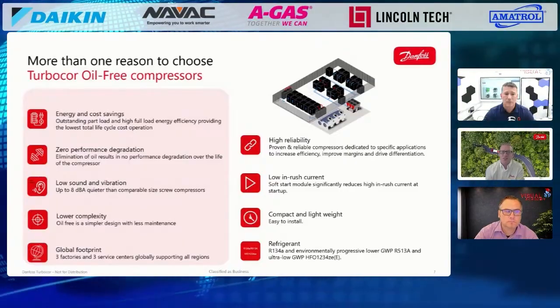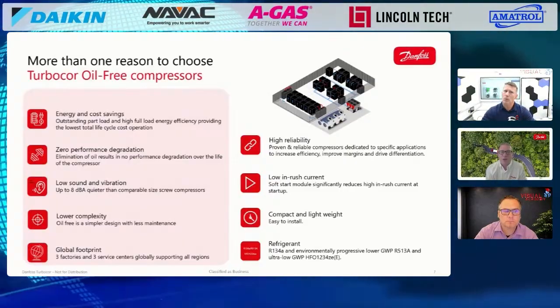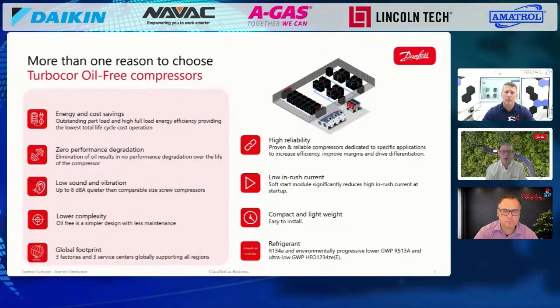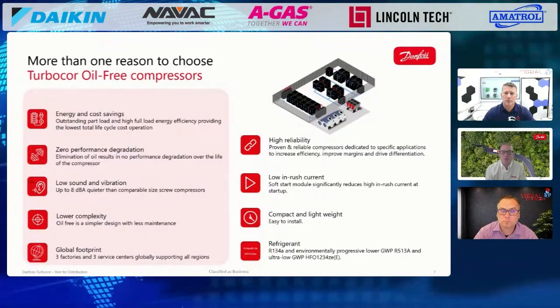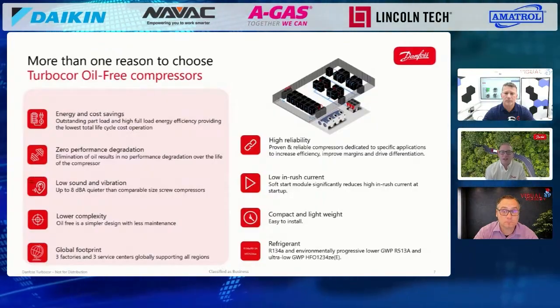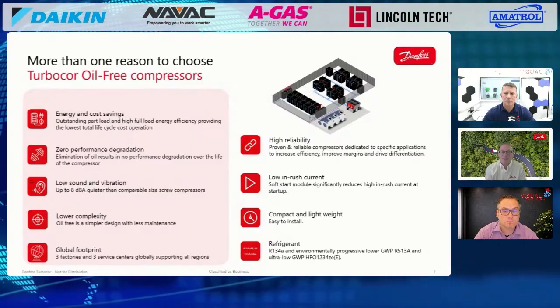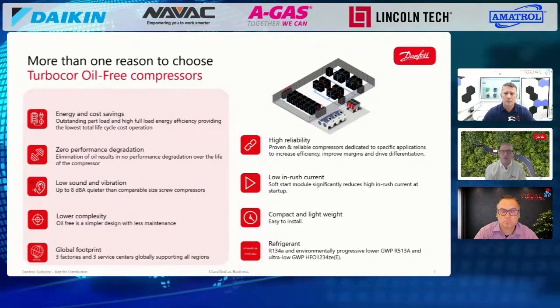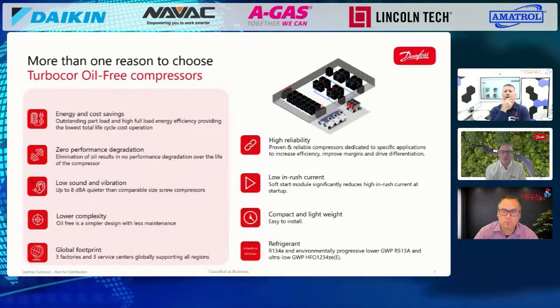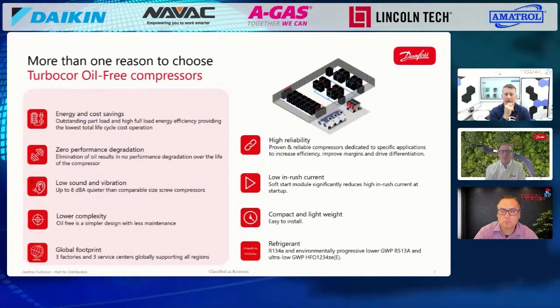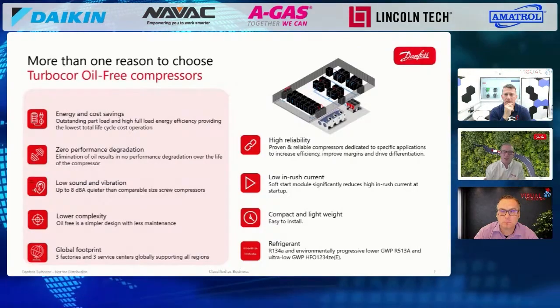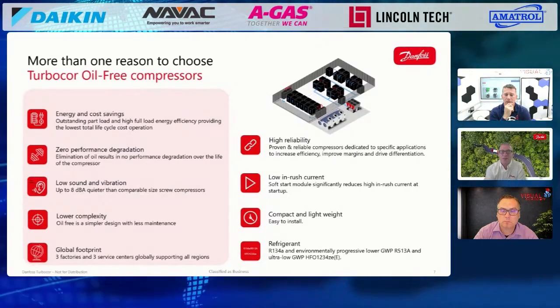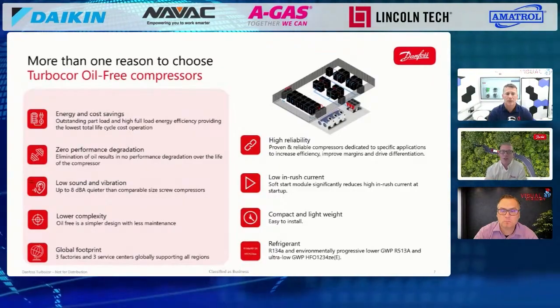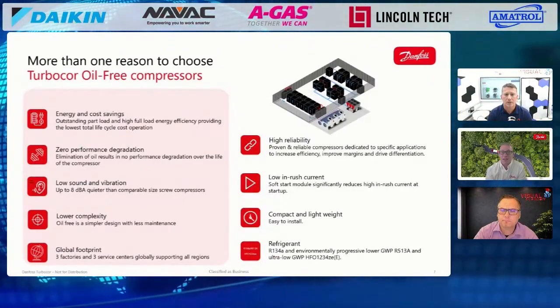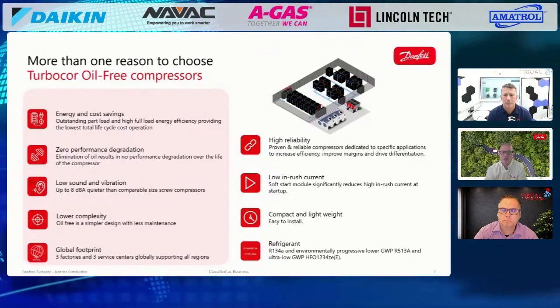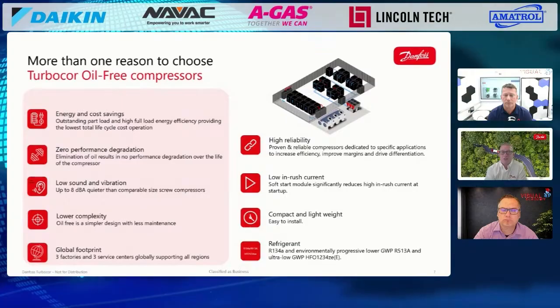There are studies showing that with an oiled compressor, chiller, or system, you'll lose around 5% efficiency and performance in 5 to 10 years, and 10% in 10 to 15 years. That's significant over the lifetime. As these compressors and chillers are designed for longer lifetimes and full serviceability in the field, you want to make sure you maintain performance, especially in high energy usage applications, staying efficient throughout the lifetime.